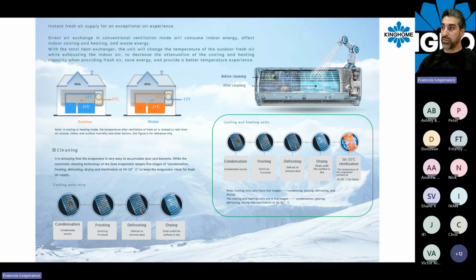The step after is drying that coil. So we will still bring in some warmer temperature to that coil and start to keep it completely dry, making sure it's clean. And then the last step will be to do some sterilization. So the heating point of that coil will rise up to 50 to 55 degrees Celsius. So it will be red hot for a couple of minutes, making sure that will kill any bacteria, make sure we don't have mold staying there.